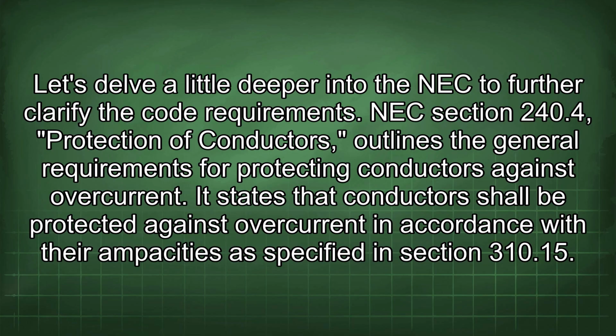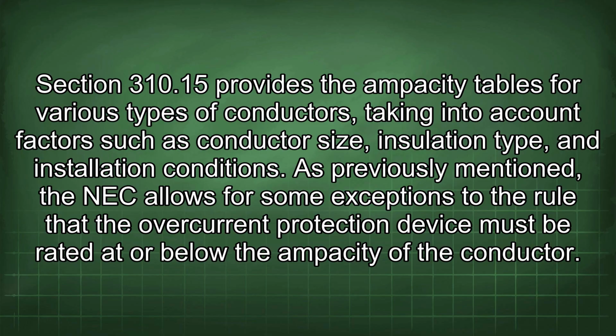Let's delve a little deeper into the NEC to further clarify the code requirements. NEC Section 240.4, Protection of Conductors, outlines the general requirements for protecting conductors against overcurrent. It states that conductors shall be protected against overcurrent in accordance with their ampacities as specified in Section 310.15. Section 310.15 provides the ampacity tables for various types of conductors, taking into account factors such as conductor size, insulation type, and installation conditions. As previously mentioned, the NEC allows for some exceptions to the rule that the overcurrent protection device must be rated at or below the ampacity of the conductor.